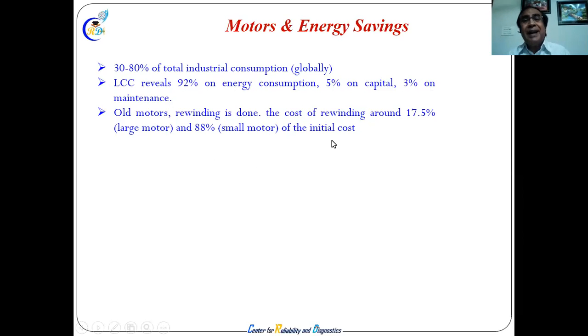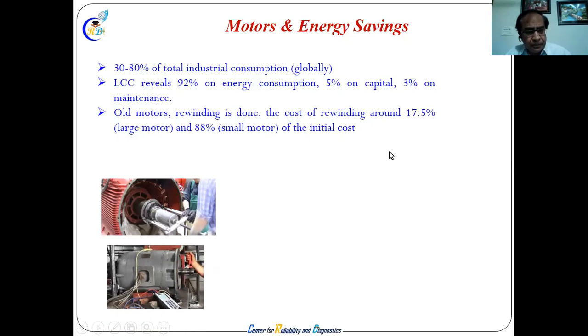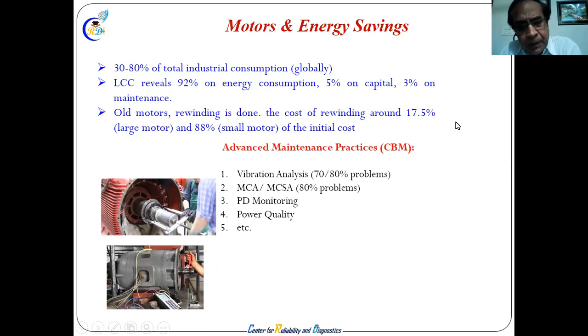Old motors, rewinding is common. Arey motor kharab ho gaya, winding karke le aao. More rewinding, more energy consumption for that motor, because every time there are human errors, you cannot wind the motor the way it was in the factory when it was shipped to you. So that is possible. In a large motor, the cost of rewinding is about 18 to 20% of the initial cost. Rewinding is done on all motors. That is very dangerous for the energy savers.